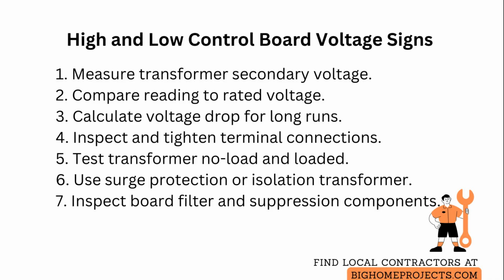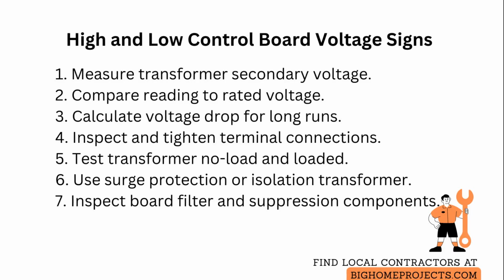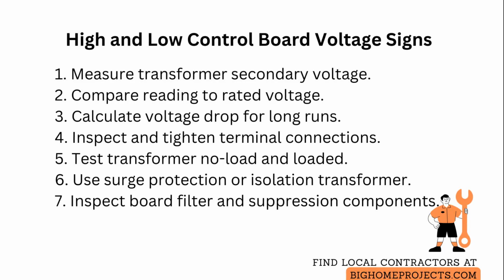Use an isolation transformer or surge protection device if you observe transient high voltage spikes. Document spike magnitude with a transient voltage recorder where possible to verify whether spikes coincide with switching events, nearby heavy motor starts, or lightning-induced surges.